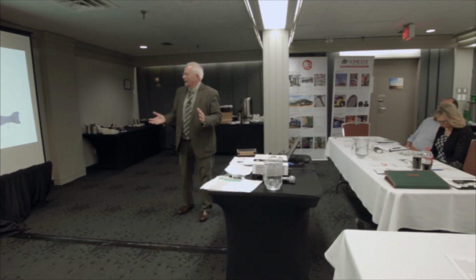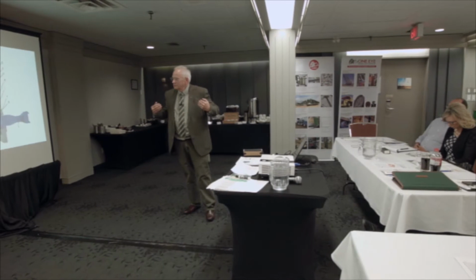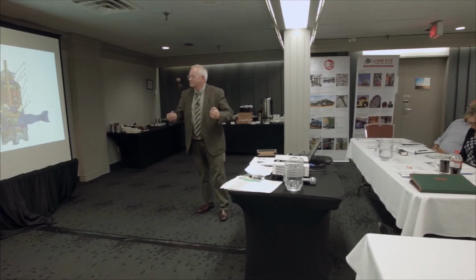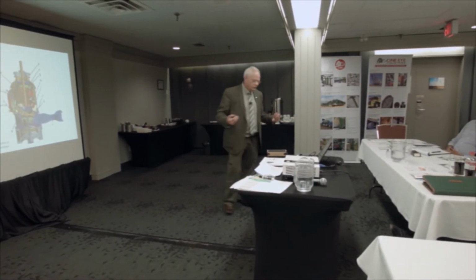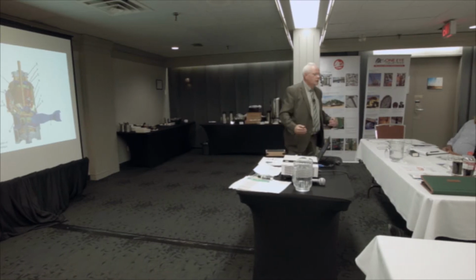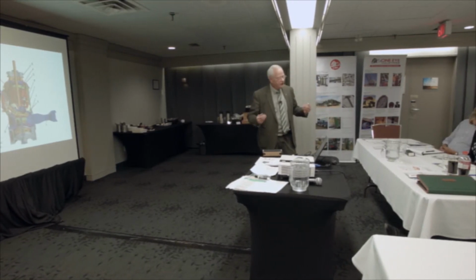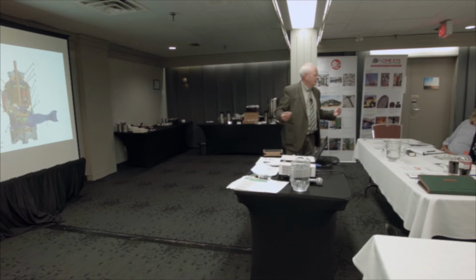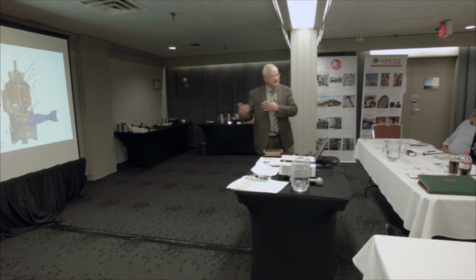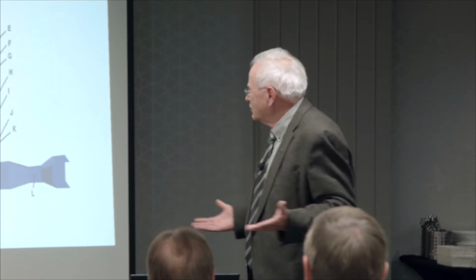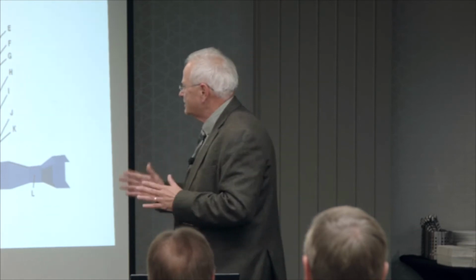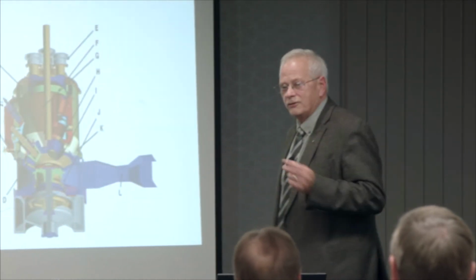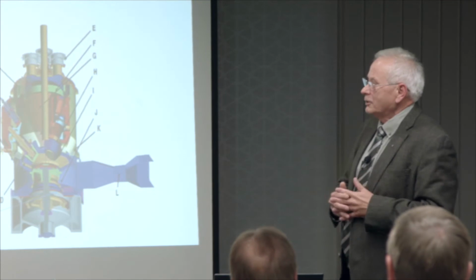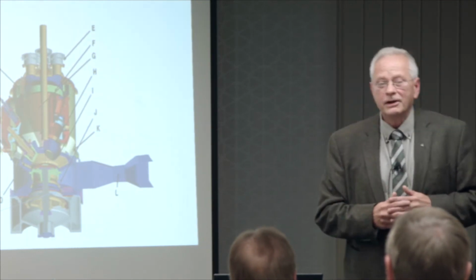I'm retired now, but when I was trying to budget for maintenance on this plant, I said, what we really should do is budget $85,000 a year for maintenance. And they said, well, why is that? And I said, because that's the insurance deductible. Because the work that we're doing is not paying for it, right? And again, as the units are getting older, we're getting more failures. In that plant, we're basically getting 1 failure a year.